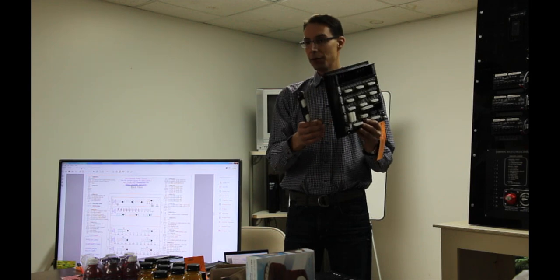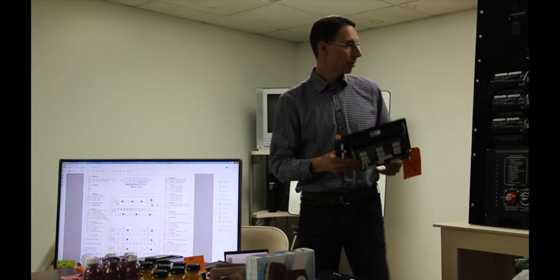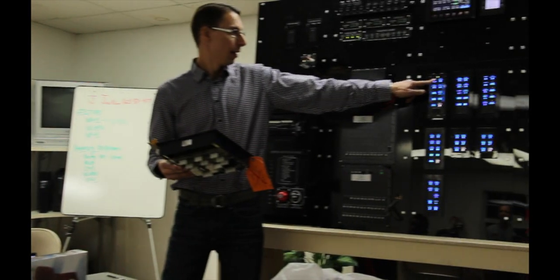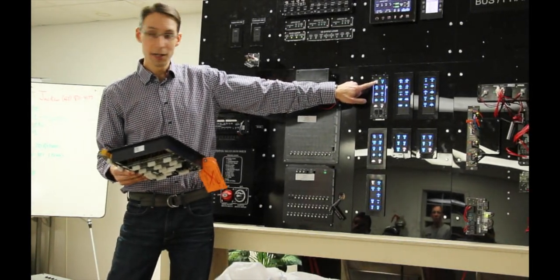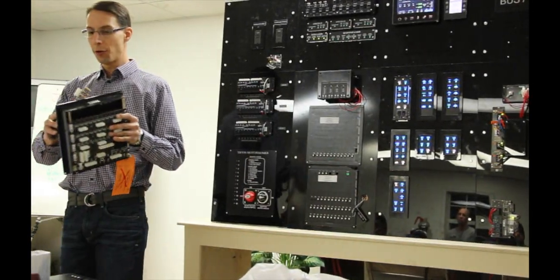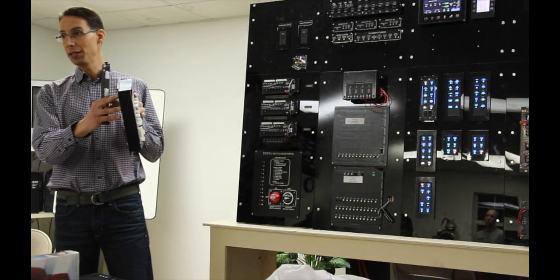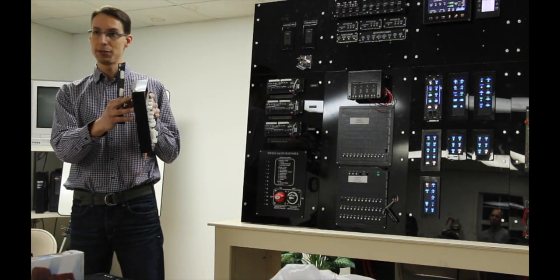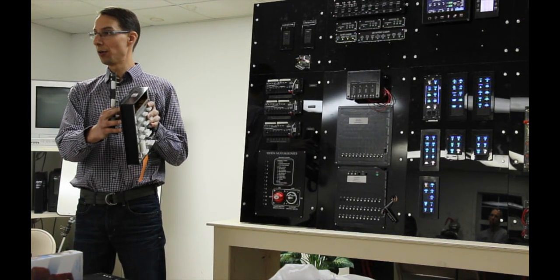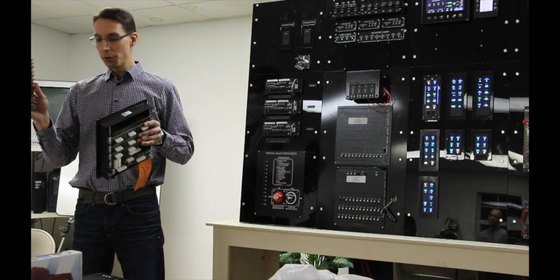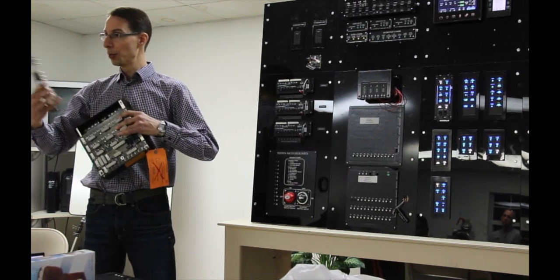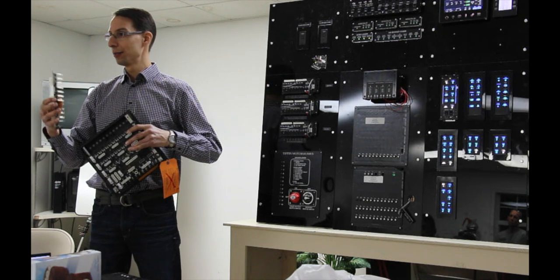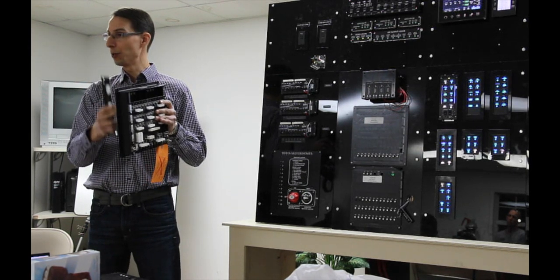So you can take a look when I pass it around, the driver card in there. What if you had an issue where you were turning the light on and off like this and it was changing color, but you went to the control panel and you didn't even see this green LED turn on and off? Like entry lights is number two. It's not even turning on and off here. Don't go any further trying to test the output of this because it's probably not this. It's going to be an issue on the driver card.